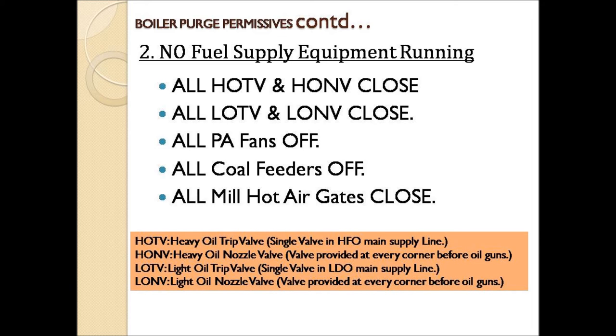To avoid that, all LOTV and LONV should be in closed condition. LOTV is the light oil trip valve, a single valve in the LDO main supply line. LONV is the light oil nozzle valve, provided at every corner before the oil guns. Similarly, all HOTV and HONV should be in closed condition. HOTV is the heavy oil trip valve, a single valve in the HFO main supply line. HONV is the heavy oil nozzle valve, provided at every corner before the oil guns. Apart from this, all PA fans should be off, all coal feeders off, and all mill hot air gates should be in the closed position.